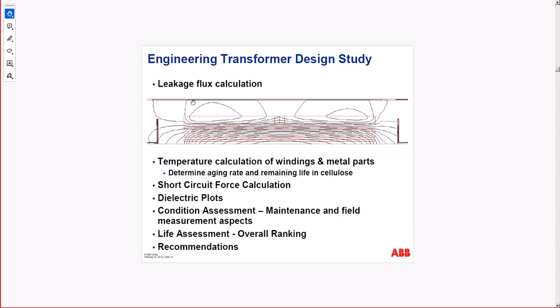So if you have that, the leakage flux will induce a voltage in the tank, and the tank is grounded, so you will have current circulating through the tank, and that will end up heating up the tank. So overheating the tank is contributing to the total heat of the transformer. The whole efficiency of the transformer goes down, because that field that heats the transformer tank does not operate as a useful magnetic field to induce voltage in the secondary, so your efficiency goes down and you have higher losses overall, right? So heat generation over the normal temperature can be generated this way.